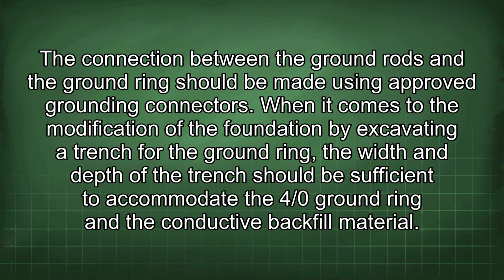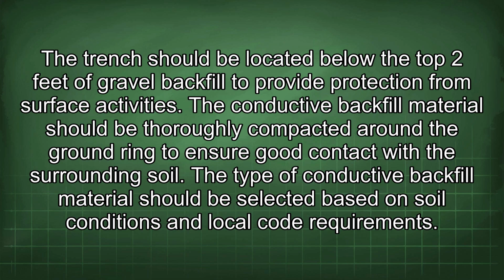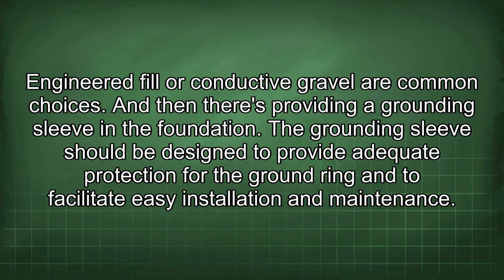When it comes to the modification of the foundation by excavating a trench for the ground ring, the width and depth of the trench should be sufficient to accommodate the 4/0 ground ring and the conductive backfill material. The trench should be located below the top 2 feet of gravel backfill to provide protection from surface activities. The conductive backfill material should be thoroughly compacted around the ground ring to ensure good contact with the surrounding soil. The type of conductive backfill material should be selected based on soil conditions and local code requirements. Engineered fill or conductive gravel are common choices.